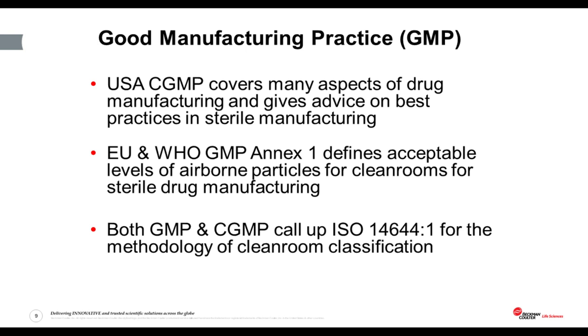The GMP rules and regulations — in North America, the C-GMP document covers many aspects of drug manufacturing and gives best advice on practices in sterile manufacturing. The European and the World Health share the same GMP Annex 1, which defines acceptable levels of airborne particulate contamination for clean rooms for sterile drug manufacturing. Both of these GMPs call up the ISO standard ISO 14644-1 for the methodology of clean room classification.